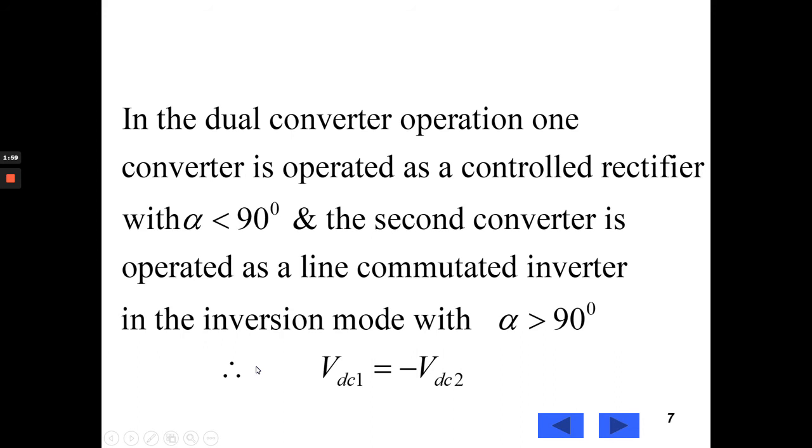In the dual converter operation, one converter is operated as a controlled rectifier with alpha less than 90 degrees and the second converter is operated as a line commutated inverter in the inversion mode with alpha greater than 90 degrees.